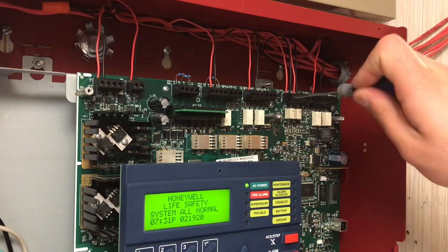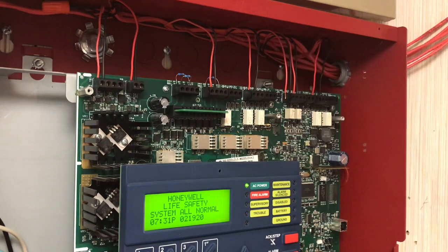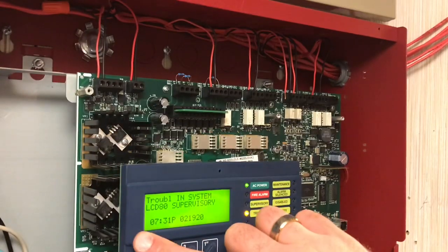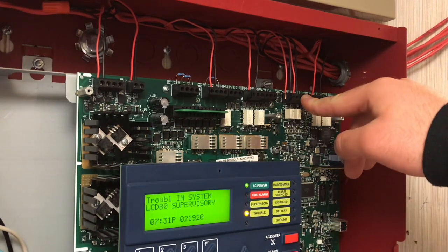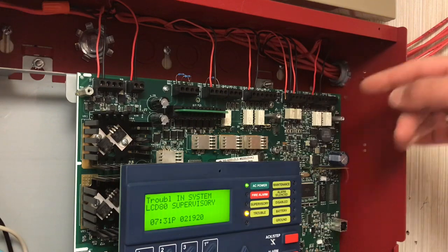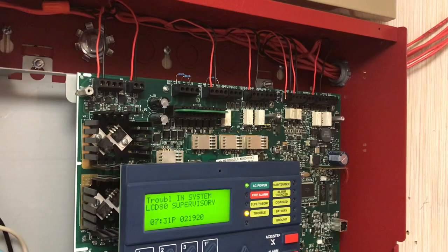Now I'm going to show you what happens if I remove the IN terminal — this is coming from the annunciator. Once again LCD-80 Supervisory trouble, however the annunciator is saying the exact same thing as the panel; it's not saying 'communication fault.' That's because it's still getting its communication — it's the return conductors going back to the panel that are affected.